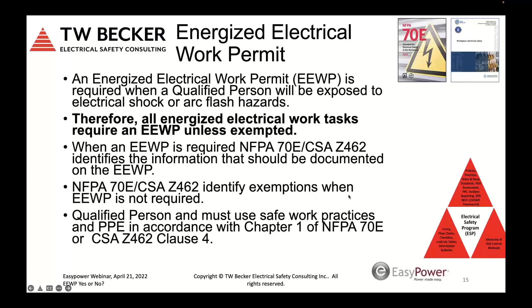They're separate requirements. The justification noted in 70E and in Z462 is justification for energized work, and it says demonstrating that de-energizing introduces additional hazard or increased risk, and I've listed the examples that are noted: life support systems, emergency alarm and security systems, hazardous location ventilation for flammable vapor emission or declassification. Then the second justification for energized work is infeasibility due to equipment design or operational limitations, such as diagnostics and troubleshooting, or a continuous process that would be completely shut down. These examples are even controversial depending on who you talk to. Well, Terry, if we don't turn the power off and there's an abnormal condition, the power is going to be turned off anyways. Well, what's the consequence of that? So again, I'm just embellishing and talking about the listed justifications.